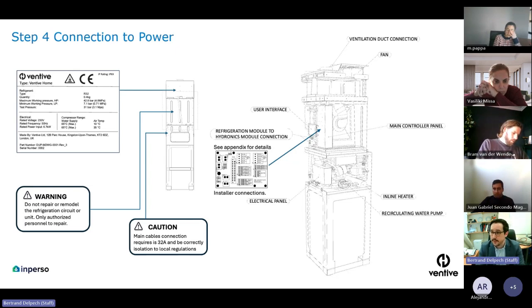If we add the fan on top of this, we are above the 13 amp limit. And also we have a backup heater that we might need to use in some situations, which will take the totality of the power consumption of the heat pump to about 3 kilowatts. But this might not happen on some of the sites, but we need to have a backup so the end user doesn't lose the use of heat during the project. So it's more a safety measure to make sure that the tenants remain comfortable, even though we are within a research project.